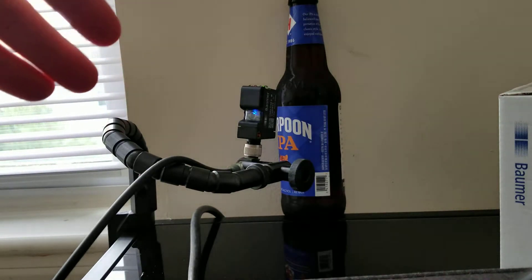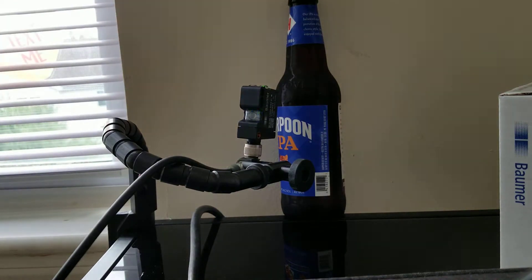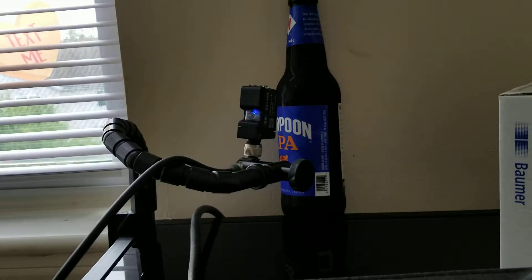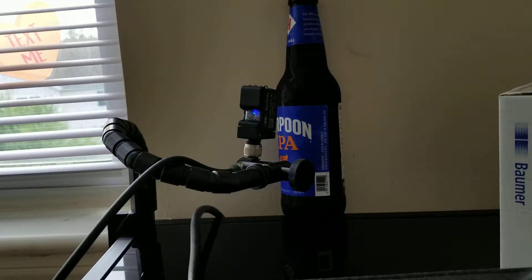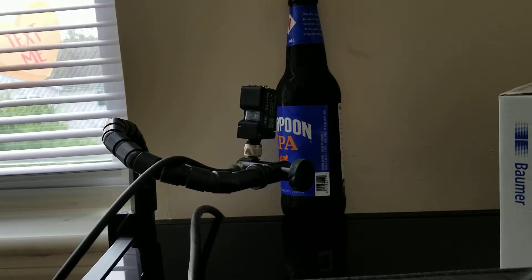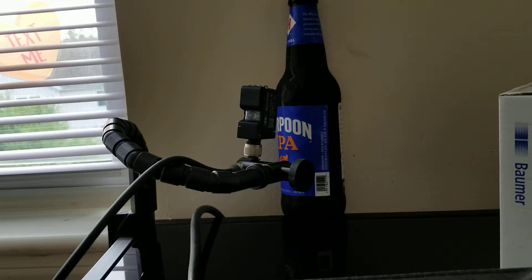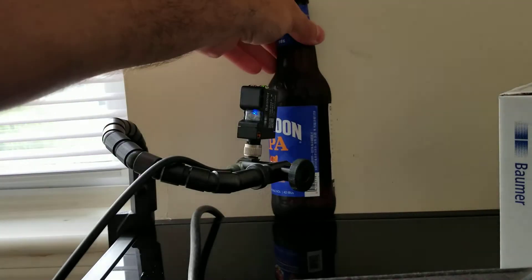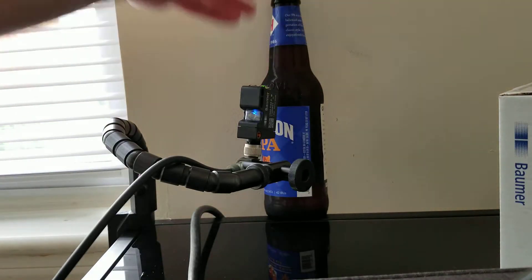One solution in a dirty environment or a wet environment such as beer manufacturing would be to use an ultrasonic sensor instead of a photoelectric sensor. They have longer sensing ranges and they have longer blind ranges. As a result, that can give you some problems.